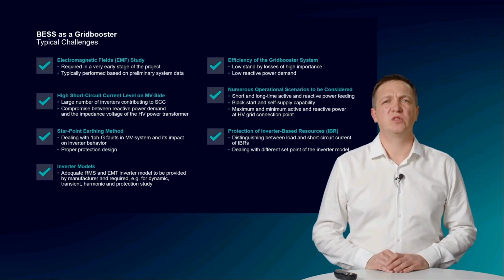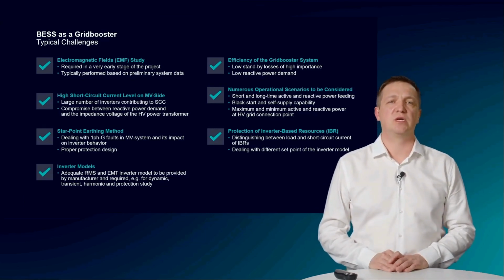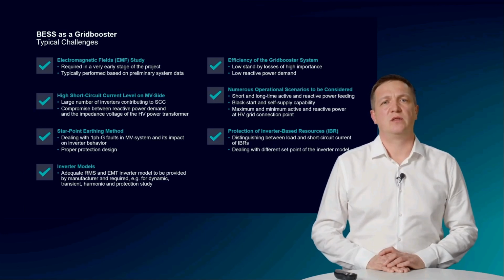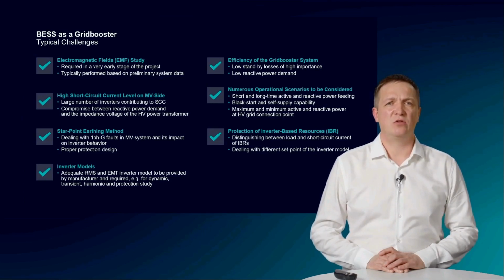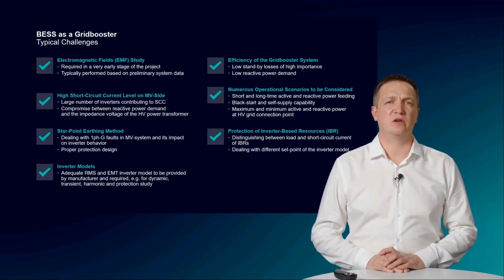The determination of losses requires very detailed information about the battery, inverter, as well as the loads connected to the auxiliary system, and it's to be calculated at different ambient temperature levels. The difference between a typical power system calculation study and the energy studies performed for the grid booster is the number of operational points. The operational points are mainly defined for the point of common coupling on the high voltage level, for instance, different active and reactive powers at different voltage levels for short time, for example, a few seconds, and long time, for example, 1 hour operation, standby scenario, black start and self-supply operation, dynamic simulations like fault ride-through and other grid compliance relevant modes.